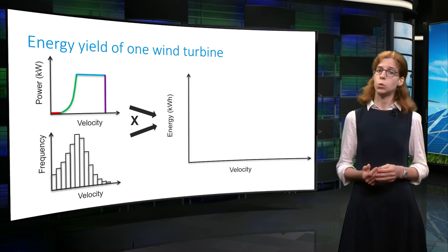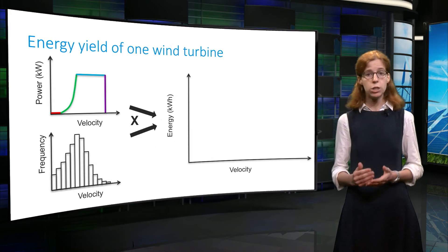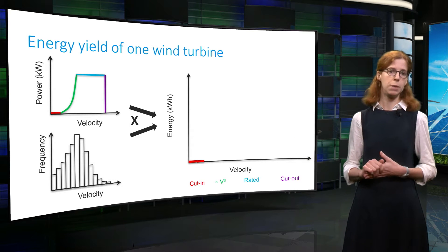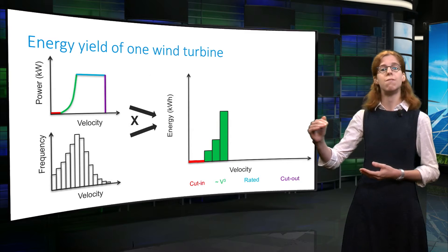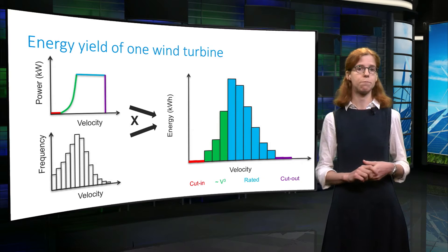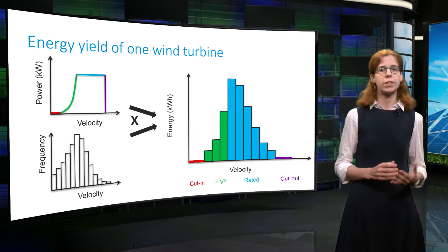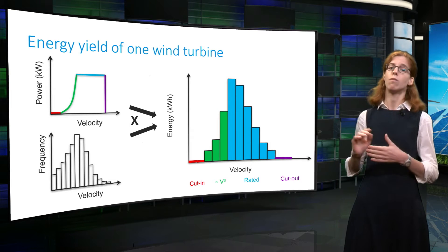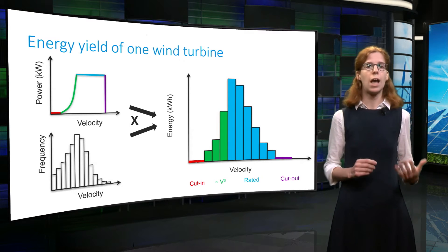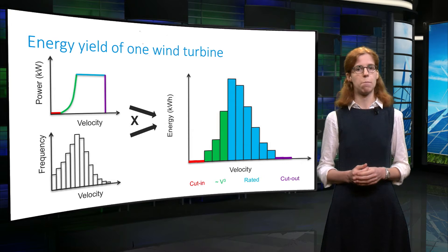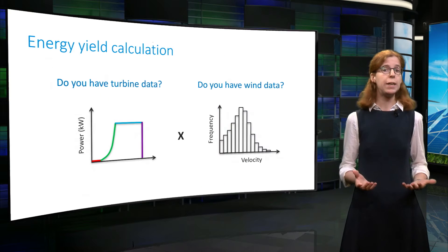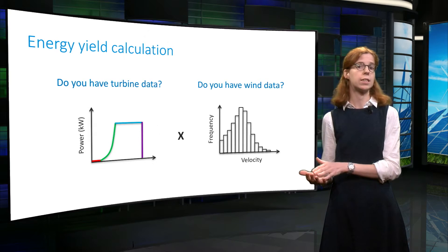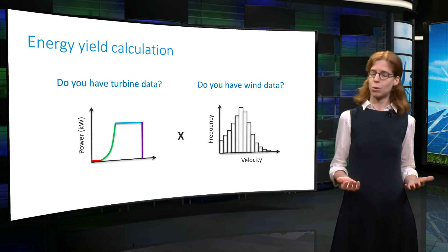Then the product of these two curves gives, for each wind speed, the total power produced — zero below a certain speed, and then positive values for the other ranges of wind speeds. If the histogram contains the wind characteristics over an entire year, then the integral of the power plot on the right-hand side gives the total annual production of the wind turbine. So generally speaking, if we know the power curve of the turbine and we know the wind characteristics at the location of the turbine, then we can compute the energy yield.